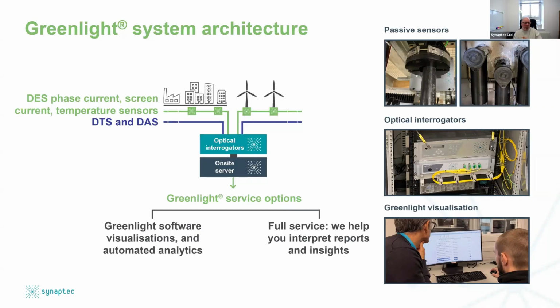It's normally much more helpful if we provide the additional service level on top of the hardware systems that says, we're going to help you see it, visualize it, interpret it, and check for things. We're going to automate all the event notifications and alarms for you, because we've pre-programmed the system with all of the typical and common failure modes that can be seen in a cable system. And then sometimes there's even a full service option where we help the customer.